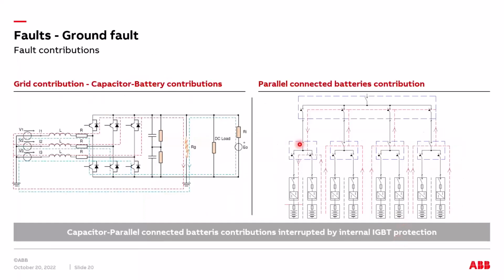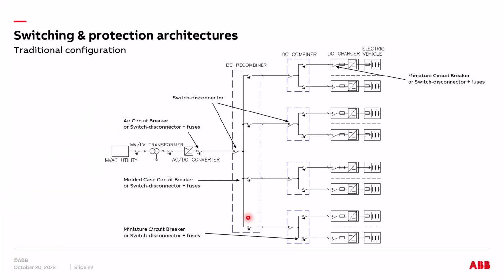If we have a ground fault, as I said, at this point, as you can see, we have a contribution coming from the grid and the contribution coming from all the other batteries installed in parallel, which can be interrupted, as I said, by the internal protection of the IGBTs. But still, we need a protective device in order to be able to interrupt the contribution coming from the grid.